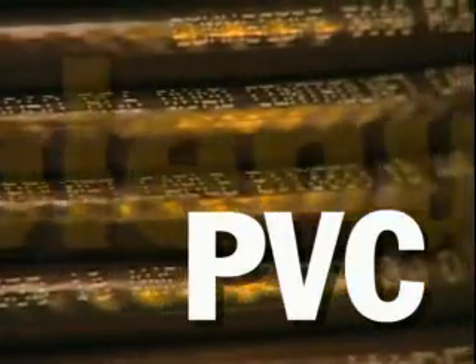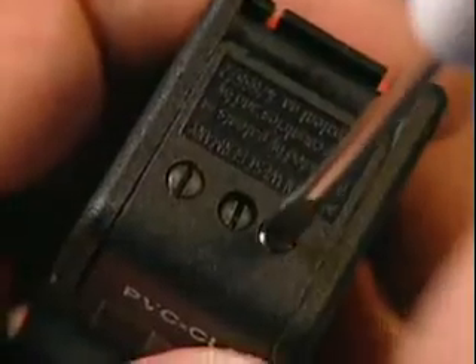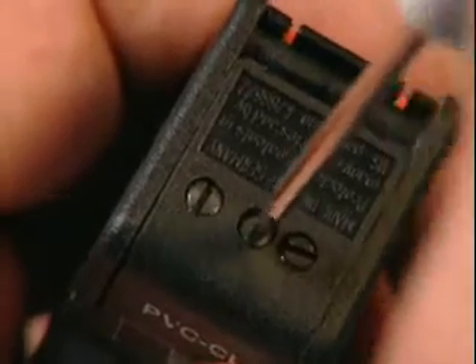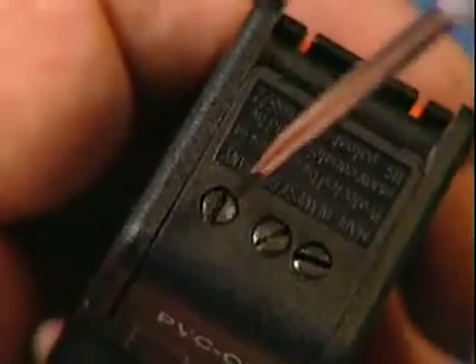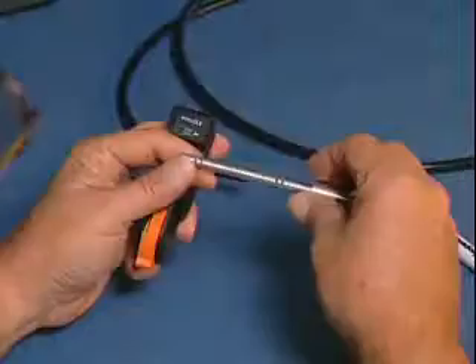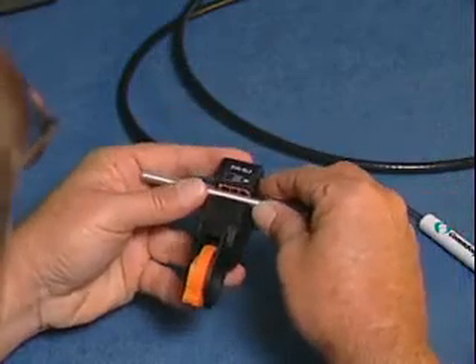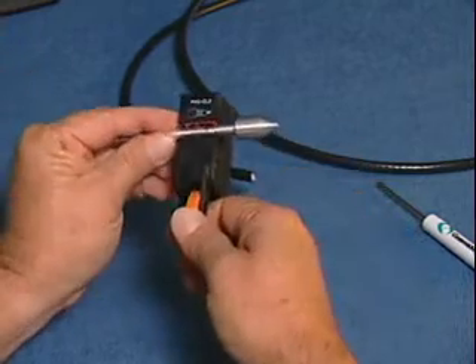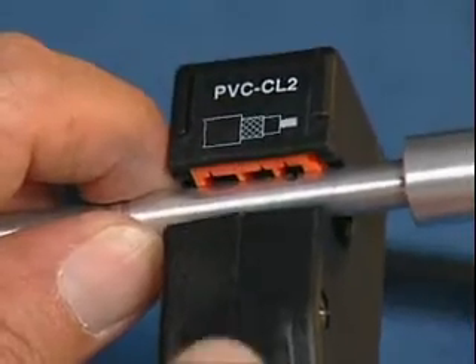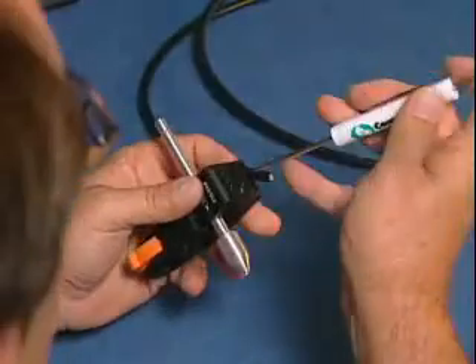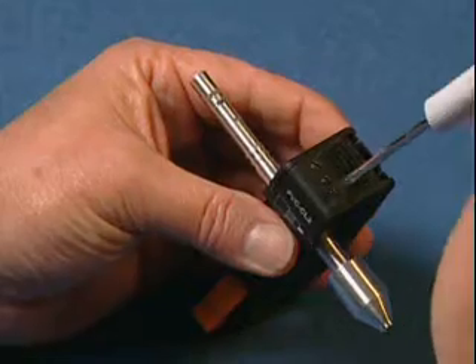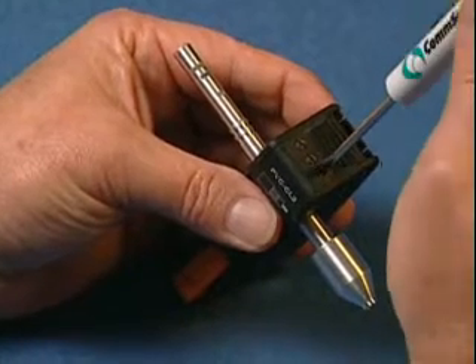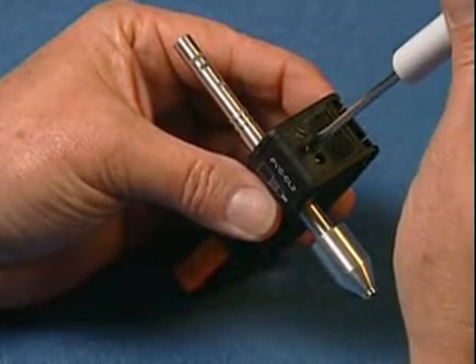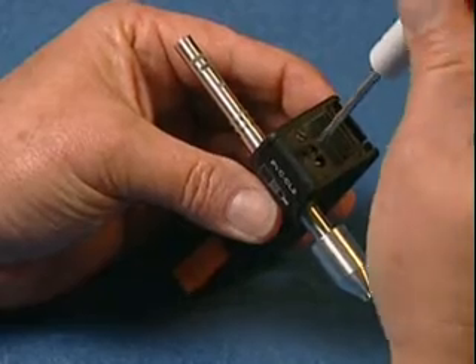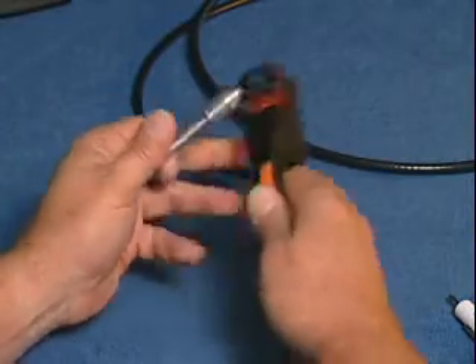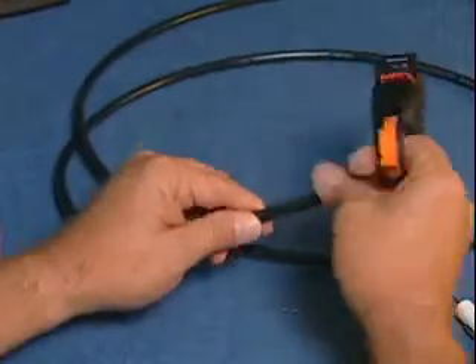To connectorize non-plenum ControlNet cable, begin by calibrating the coaxial cable stripping tool. Rotate the screws counterclockwise to bring the screw heads flush with the top of the memory cap. Place the larger end of the calibration tool in the coaxial stripper. Use your screwdriver to rotate the screws in a clockwise direction until the blades just contact the calibration tool. Remove the calibration tool and make a practice cut on the cable.